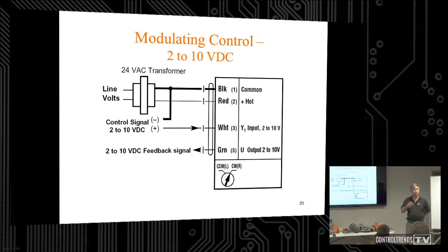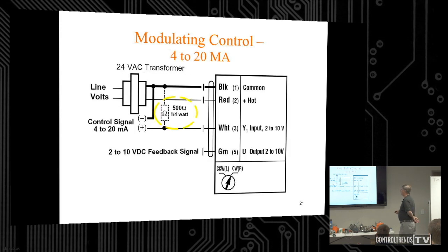Okay. So far, what's difficult? It's pretty straightforward stuff, isn't it? As long as you pay attention to what you have and what you need. Sometimes instead of having a 2 to 10, we have a 4 to 20 milliamp signal. It depends on the controller. And that just says we've got a 500 ohm load in there. Again, if you're not sure about that in your particular application, call us. We could probably guide you through this. It's not a problem. Sometimes 4 to 20 milliamp signals come on 3 wires, some on 2 wires. We have to know. There's a difference.